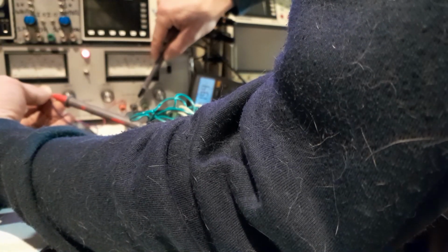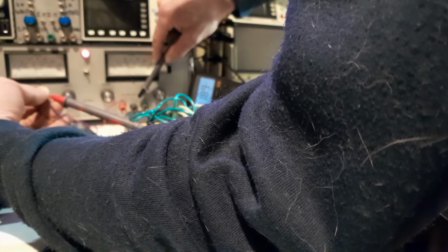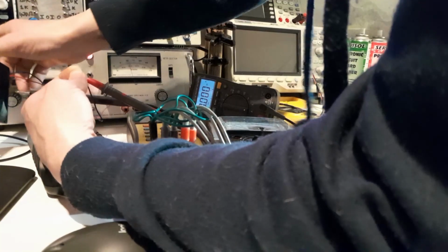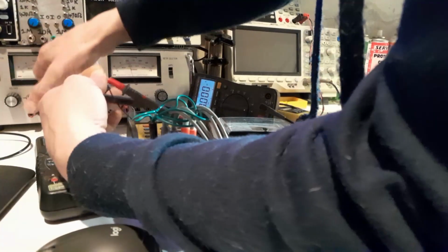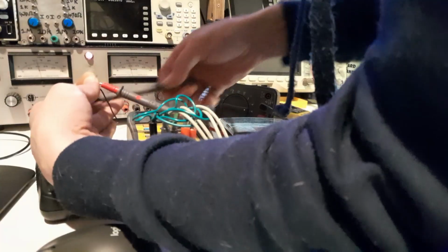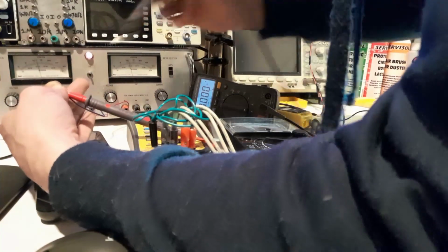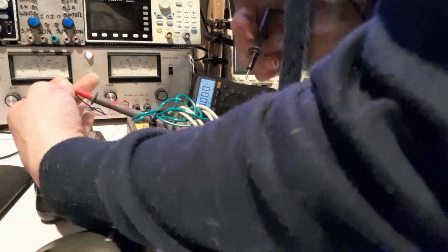So I'm wrong, it's not these fans. That's interesting, and that's with the most load on it because it's got air moving through it. A fan, or any motor with wind resistance, will take less power when you block the airflow, since there's no air moving through it anymore. You'll actually hear it spin faster. A common misconception is that when you block the flow to a fan and it spins faster, people think it's working harder. Actually it's working easier because it's got no air going through it, and that's why it spins faster, because there's wind resistance.